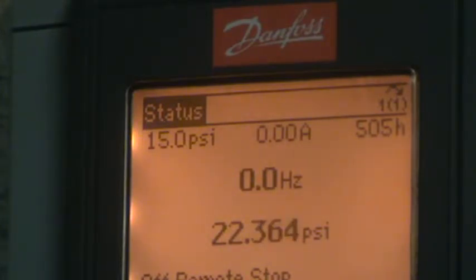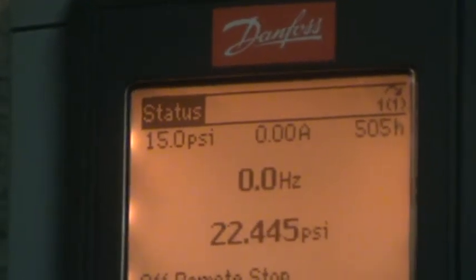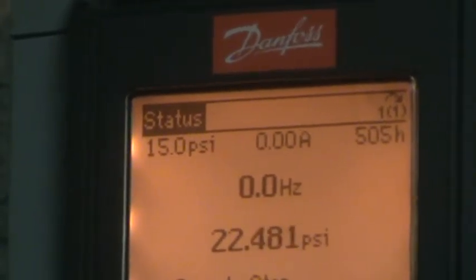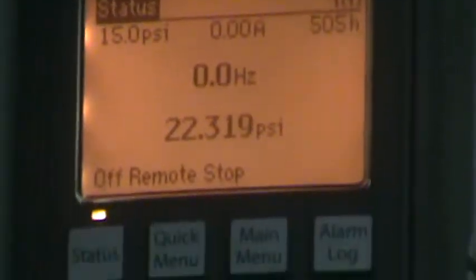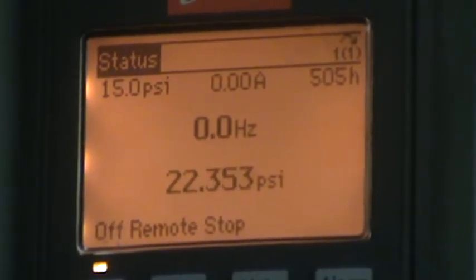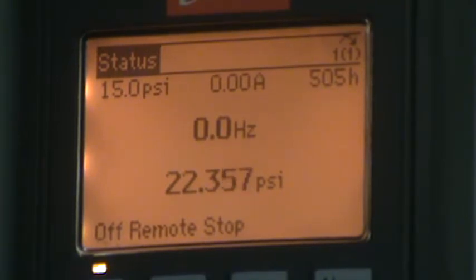So if the system isn't getting enough heat to this building, they can bring that up. They can bring that up, yes. And what is the max on the PSI? It's a 0 to 50 scale transducer. You know the system. Don't go past what? You can set it to that 50-pound max. But the pump, you only have 60 hertz of speed, so the pump will actually hit maximum speed before it'll necessarily get there.